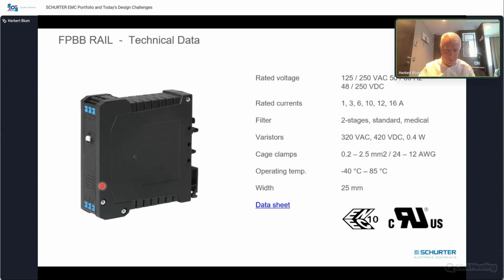It has one weak point: a plastic housing. Most filters use metal housing for better ground connection - metal housing is EMC-wise always better than plastic, that's just a fact. But we decided to use this slim form with plastic, and we integrated a printed circuit board where one side is only ground. So we have a bit of grounding, but not the same as a proper metal housing. The reason we did this is that the control cabinet itself is usually made of metal, so it's a metal enclosure, and EMC-wise it should be fine.